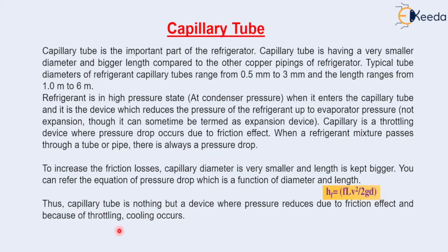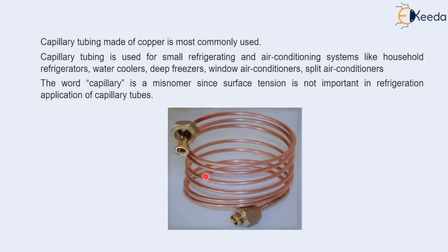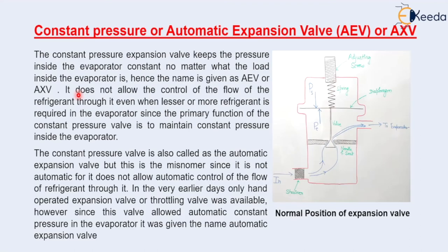Thus the capillary tube is nothing but a device where pressure is reduced due to friction effect, and because of this throttling, cooling occurs. The capillary tube is made of copper and is most commonly used. Capillary tubing is used for small refrigerating and air conditioning systems like household refrigerators, water coolers, deep freezers, window air conditioners, and split air conditioners. Note that the word 'capillary' is a misnomer here, since surface tension — which relates to capillary effect — has no relation with refrigeration application.